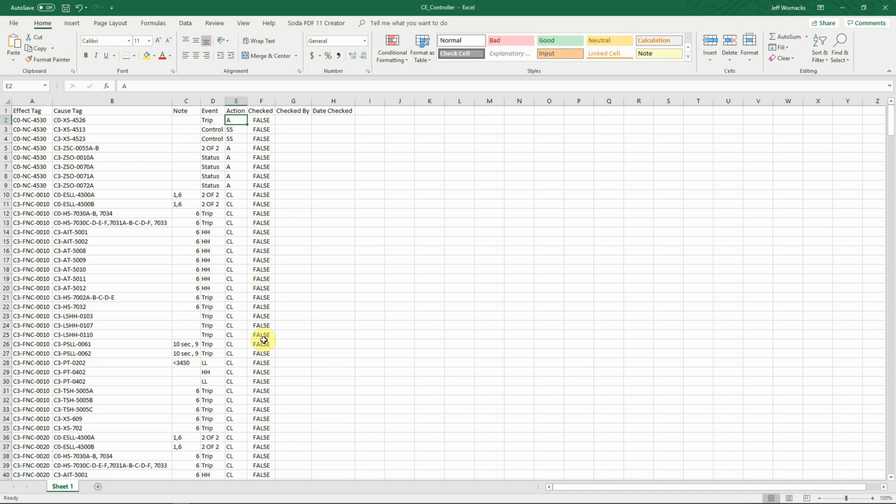Of course, when you import, it does not look at any of this information. Basically what it does is during a full import, it wipes out your full cause and effect matrix and rebuilds it, so that after you are done importing your cause and effect and you start commissioning, you're definitely not going to want to import at all. So you would add any fine tuning, any changes, anything that was missed just from the front end of the database.